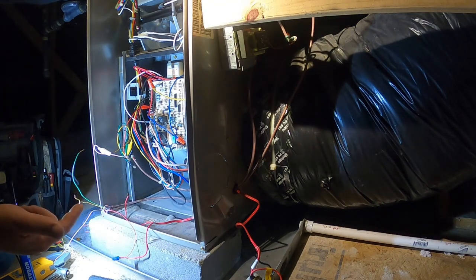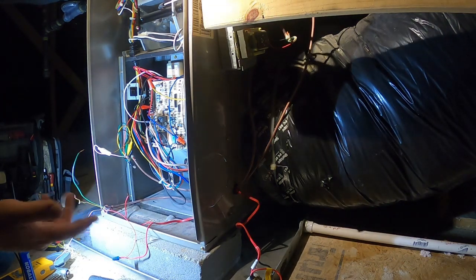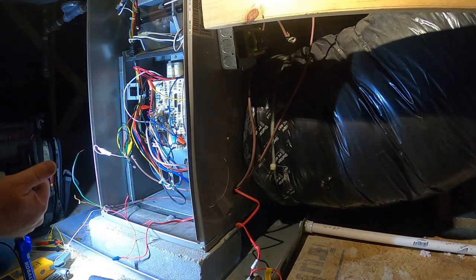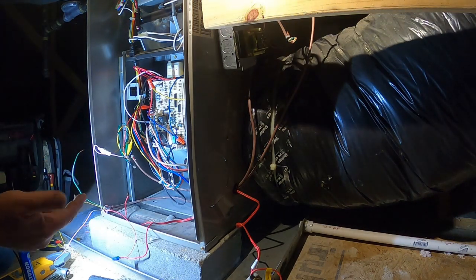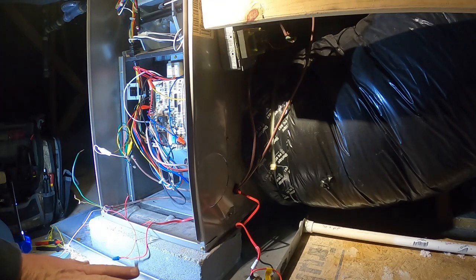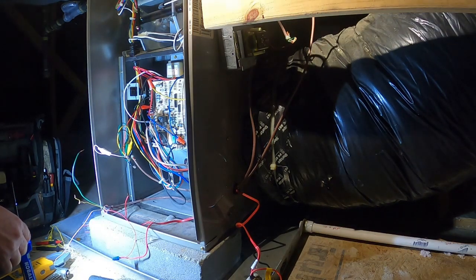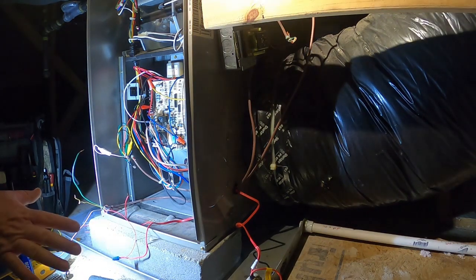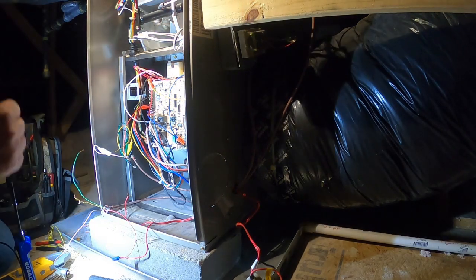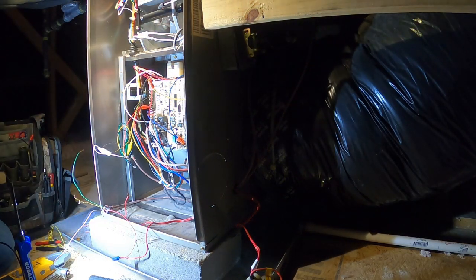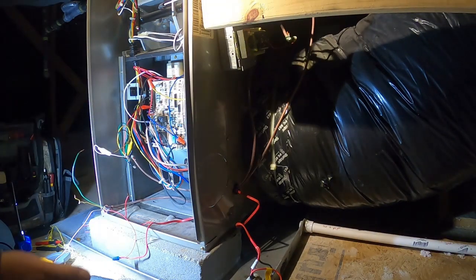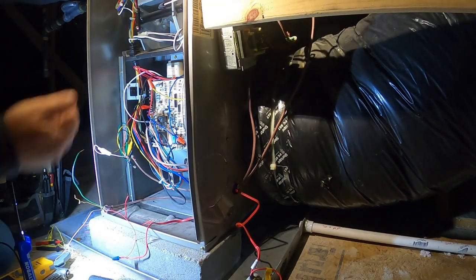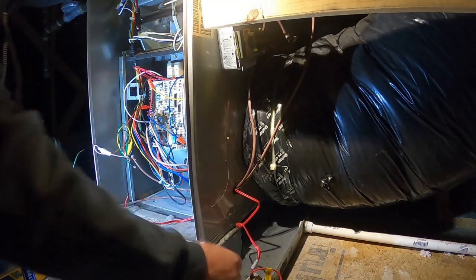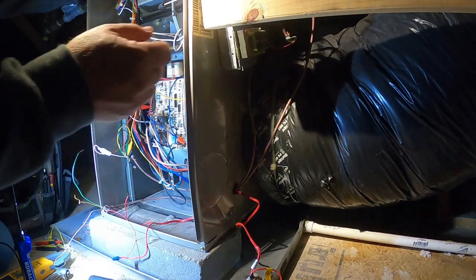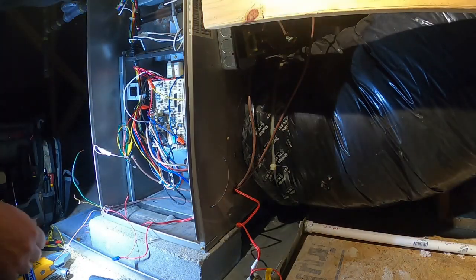Our project manager came out to quote the new system, saw the condition of the unit, saw what was going on, and told her, let's have one of our technicians come out and look at your equipment first and find out what the real problem is. And sure enough, we made the right decision. All it was a contactor, and then the transformer went bad because that guy didn't put another 3-amp fuse in it. He put a 5-amp in it, and it didn't work.